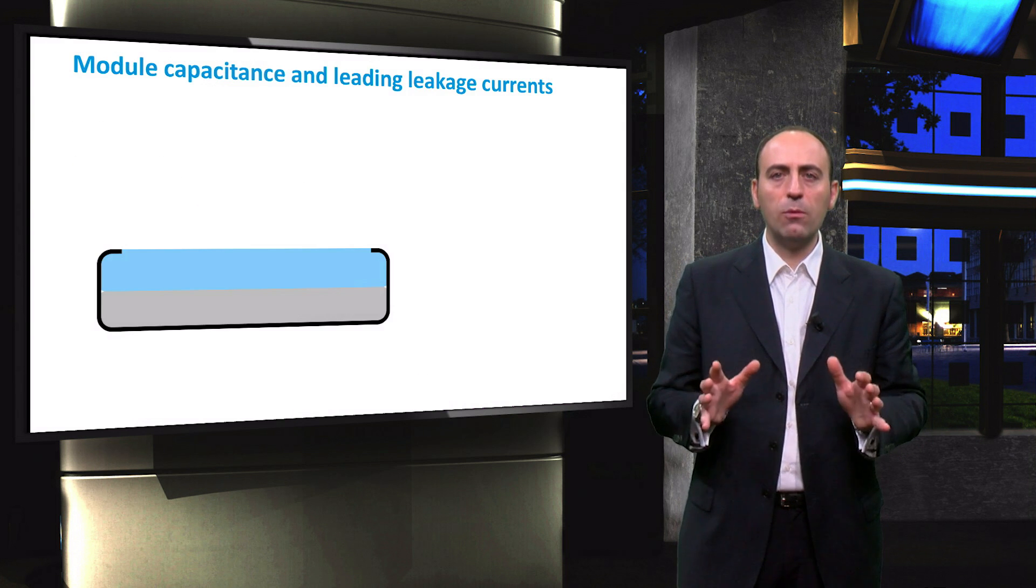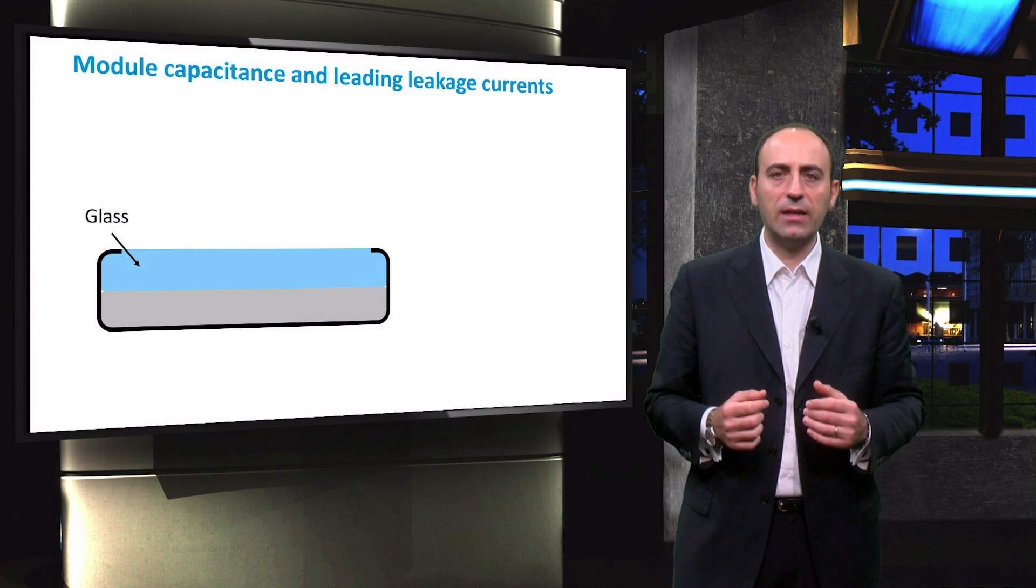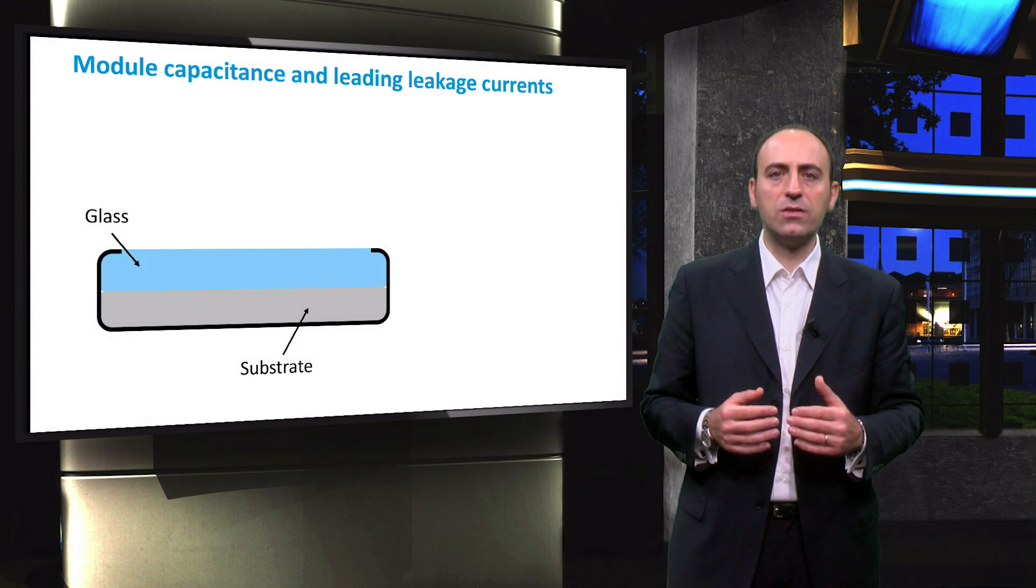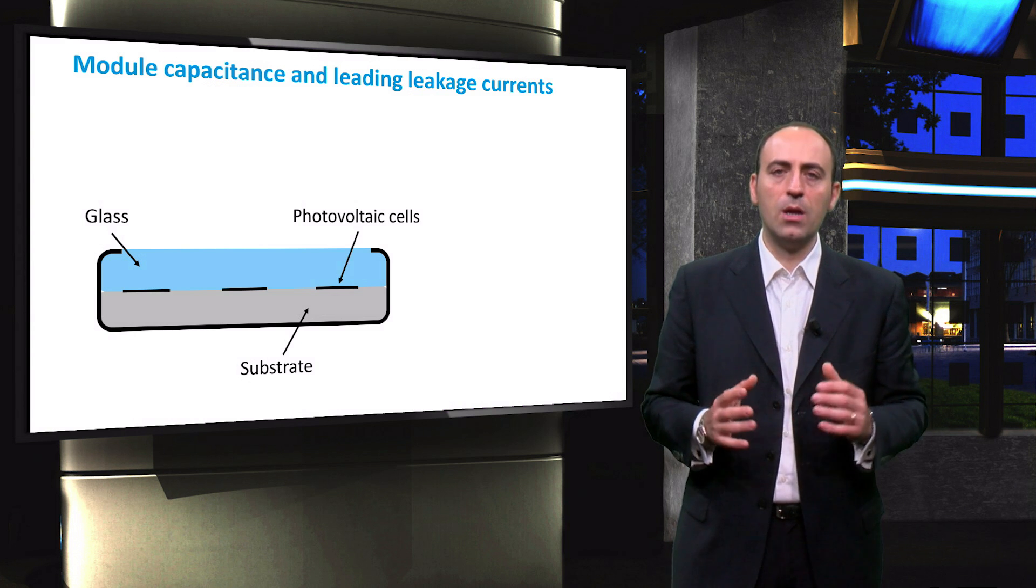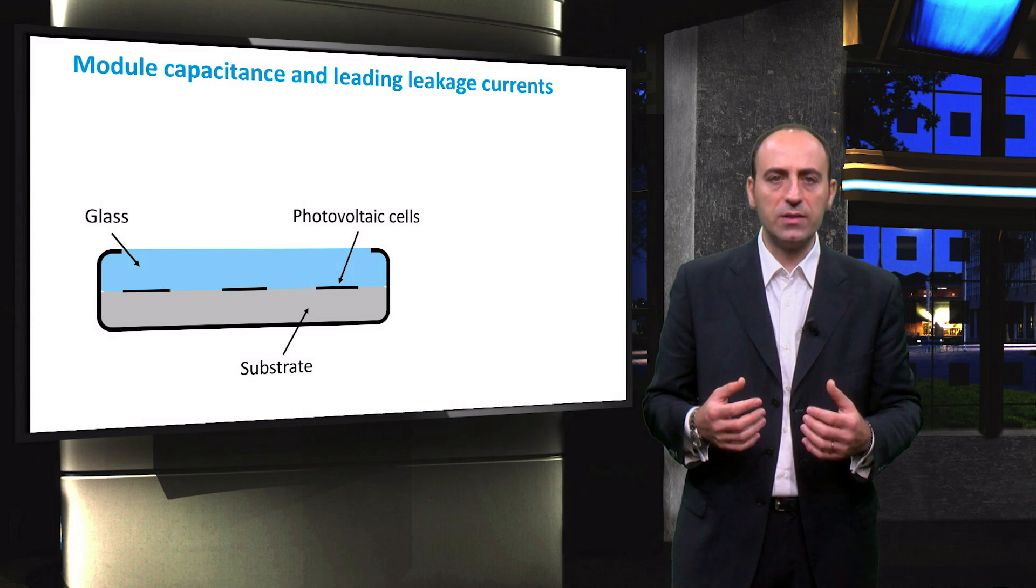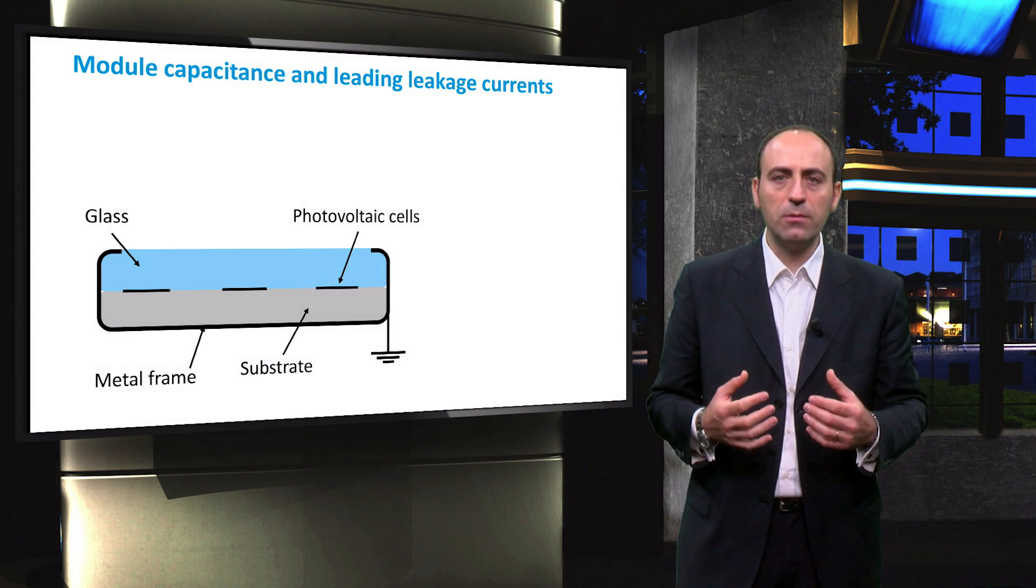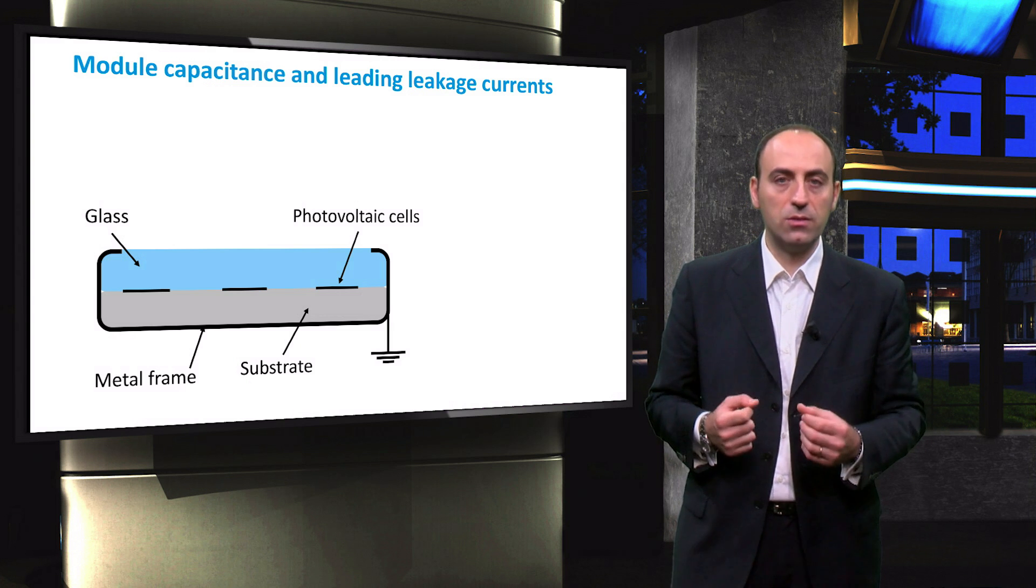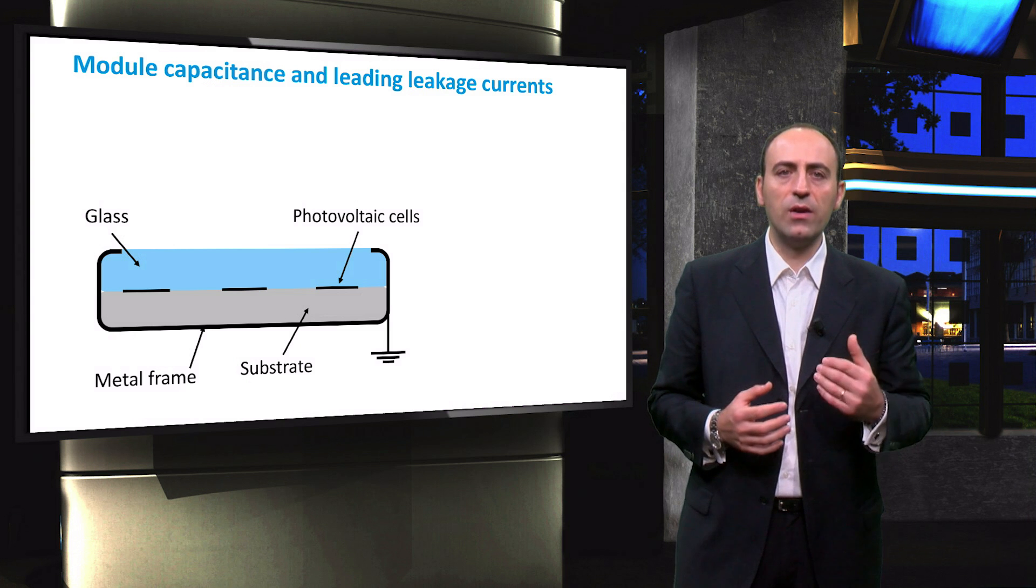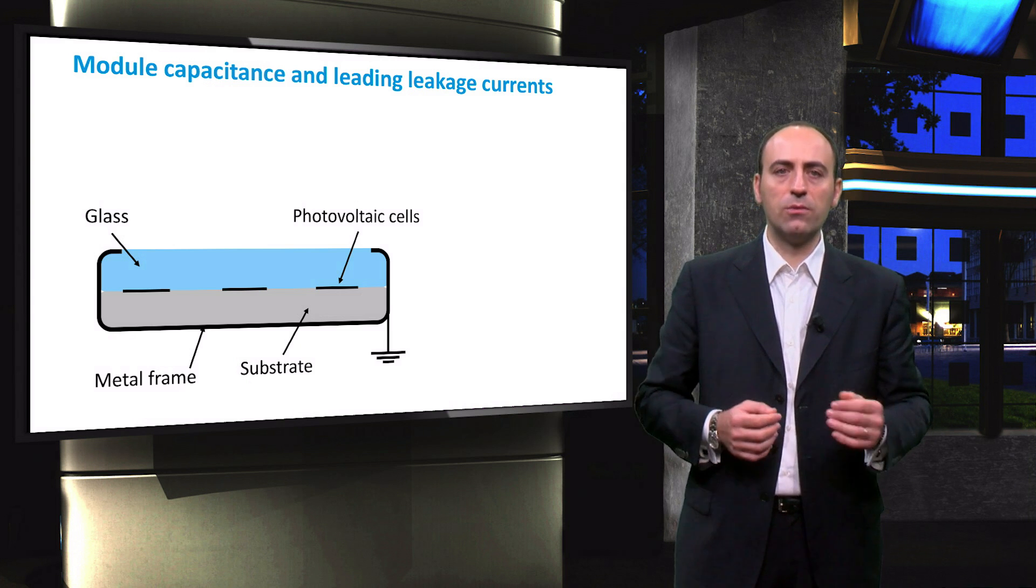A PV module is formed by different layers. A glass layer is on the top part and it lays on a substrate, and the photovoltaic cells are situated between these two levels. The PV module generates an electrically chargeable surface area, which is next to a grounded metal frame. Such an arrangement behaves as an electrical capacitor, whose capacitance is greater the larger the surface area and the smaller the distance from the grounded frame.